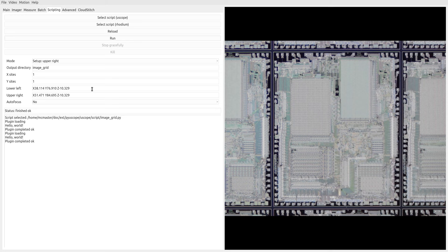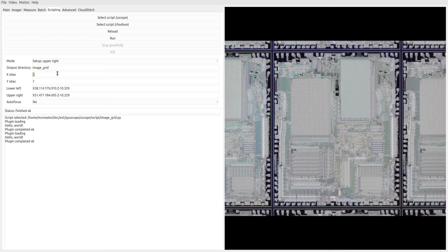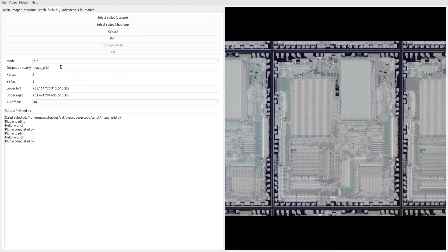The last thing that we need is we need to tell it how many sites on the X and the Y direction we have so it can calculate the X step and Y step, that is, the pitch of the scan. So we have three dies wide and two dies tall, so I'm going to put those parameters in there. With all of that ready to go, I'm going to say run, let's kick it off, and it's going to start imaging.